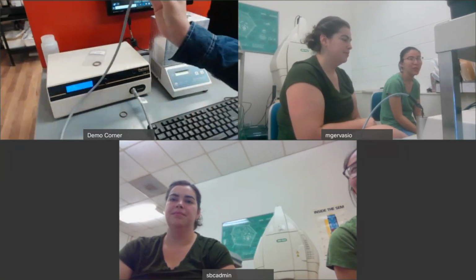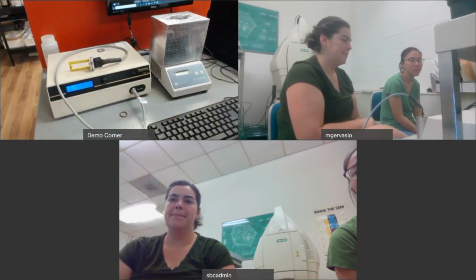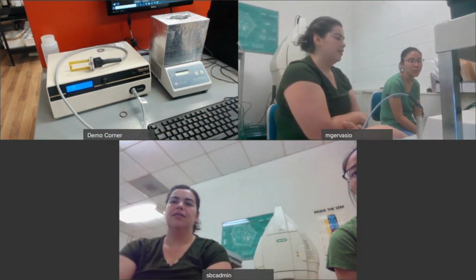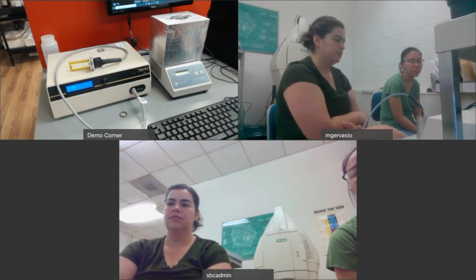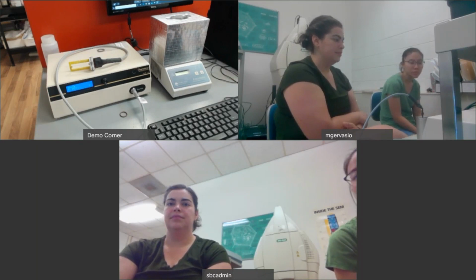Also, right now you are measuring distilled water. So after you do a proper warm-up and a proper calibration of the sensor and confirm the repeatability of your measurements, then you can try to remeasure your tap water. If you see again changes in the thermal conductivity, but you will measure, you will not calibrate with the tap water because it's not pure.